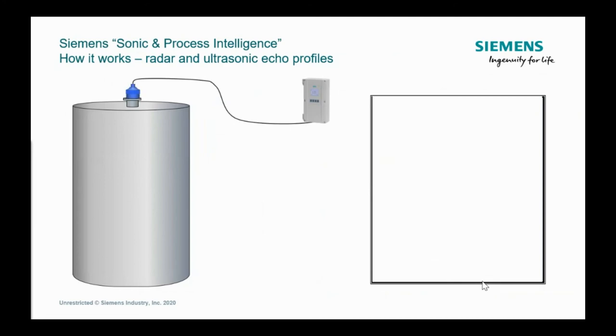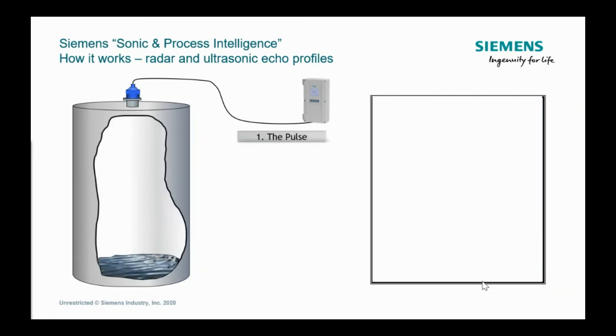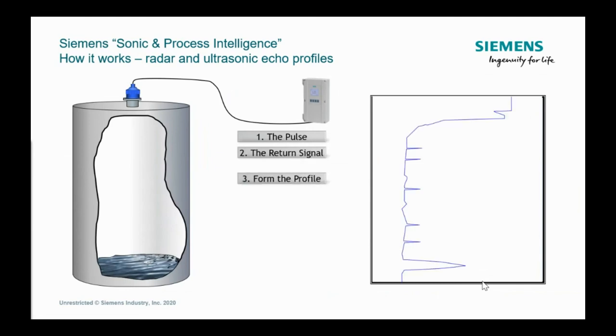Okay. So when it's making this measurement, there's a lot of things that happen behind the scenes. Number one is it's going to send out the pulse. You're going to get a return signal. Then the instrument is going to form something called the echo profile. If you've never seen this before, basically it's a visual example of what the instrument sees.